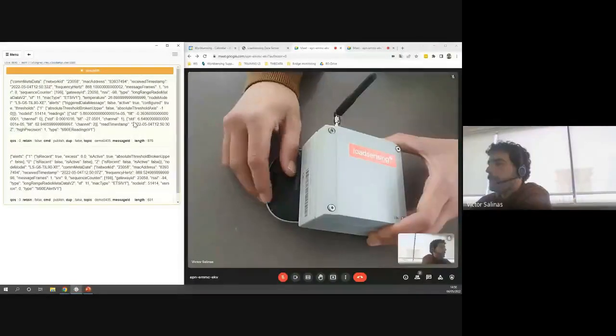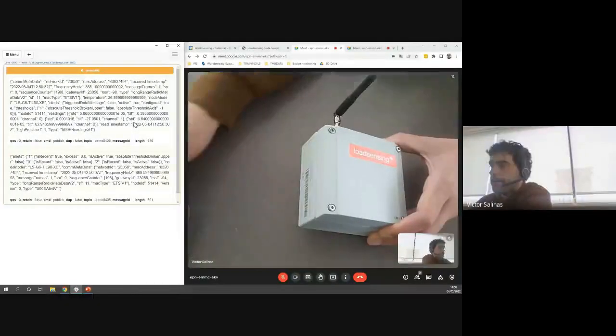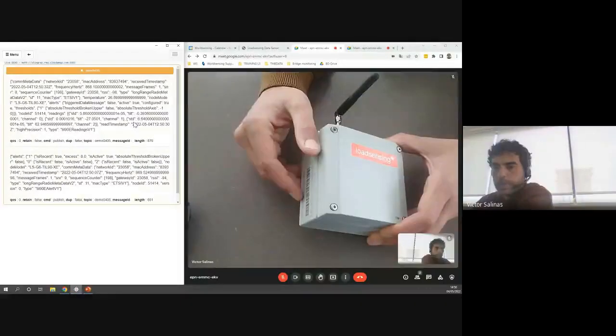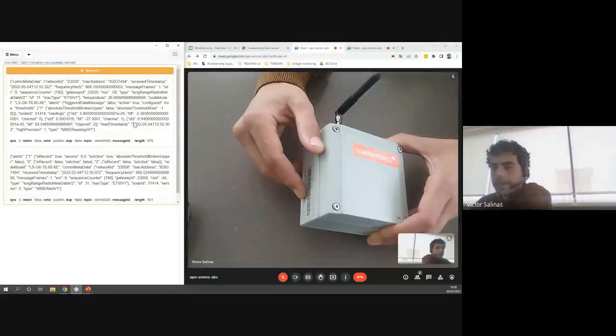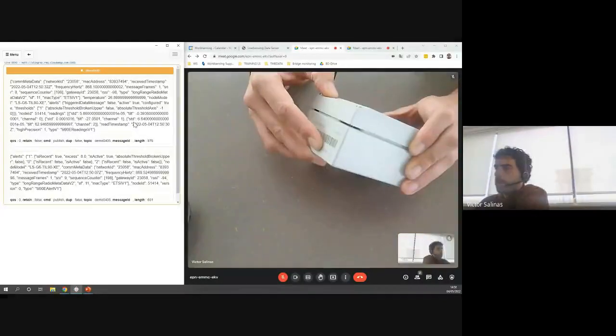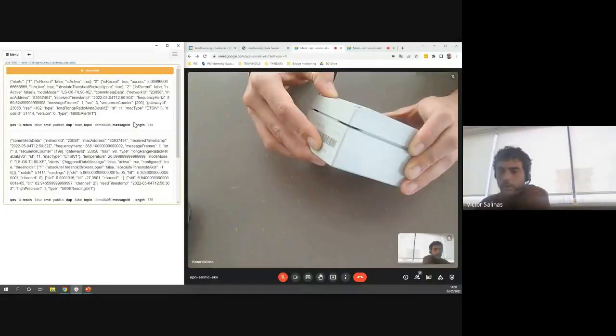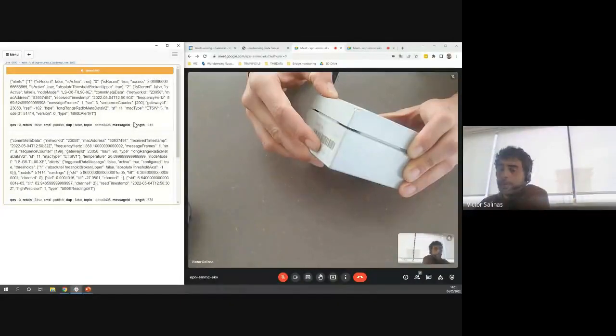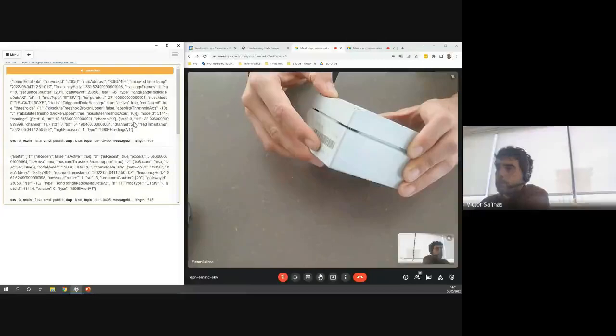Okay, what happens if we are now in an alert state, supposed to be reporting every 30 seconds, and I flip again in the I direction? As another threshold is broken, we receive another message for the I component. And now, every 30 seconds, a message with a report arrives. This message, which is basically a periodic reading, appears at a rate of 30 seconds instead of the half hour we had before.